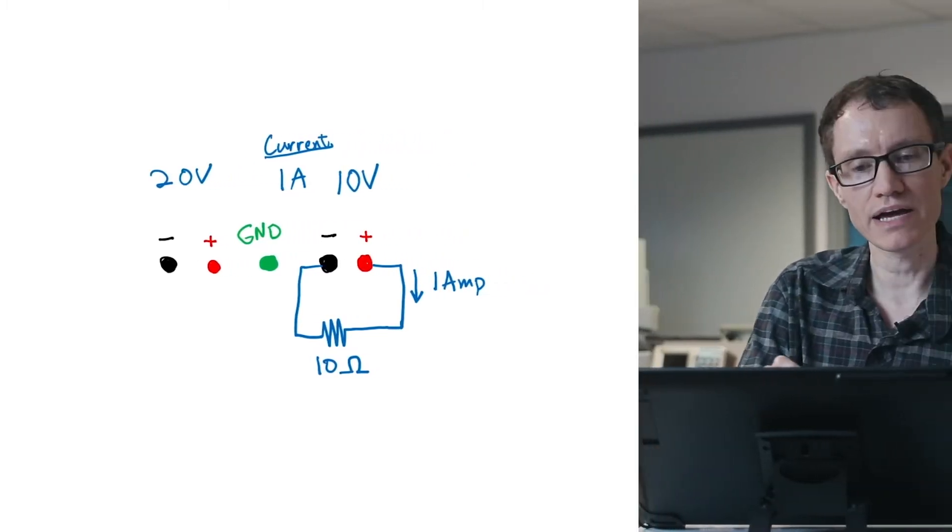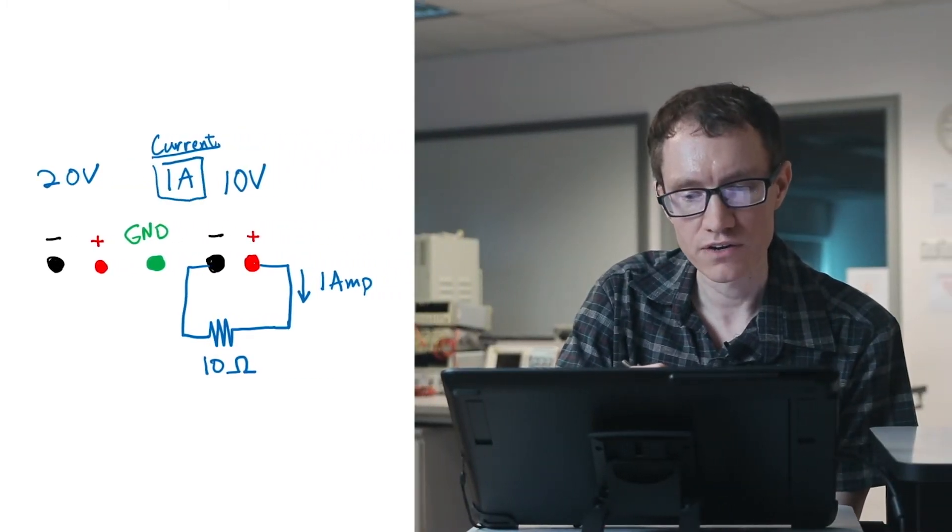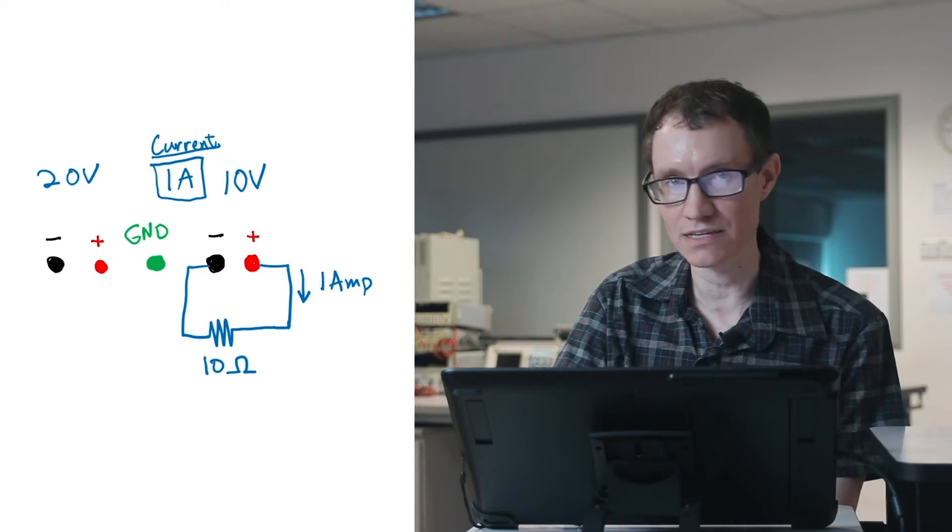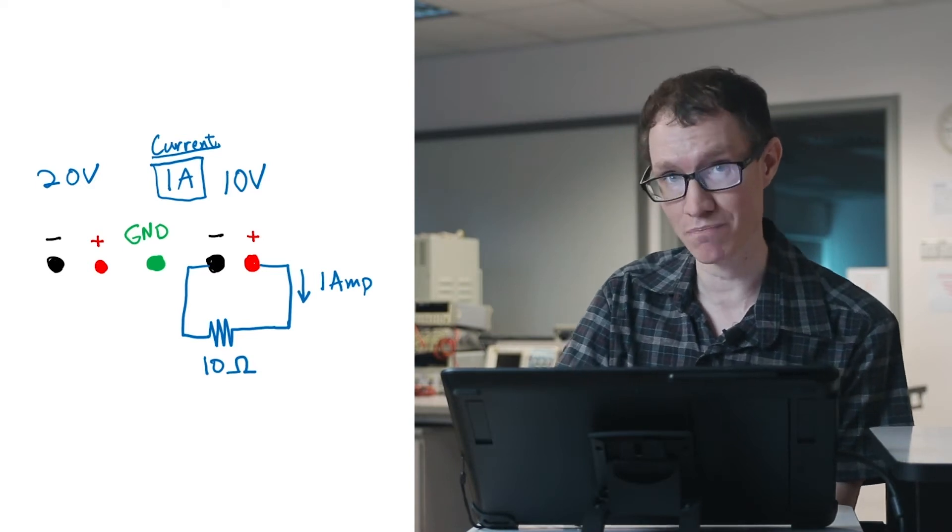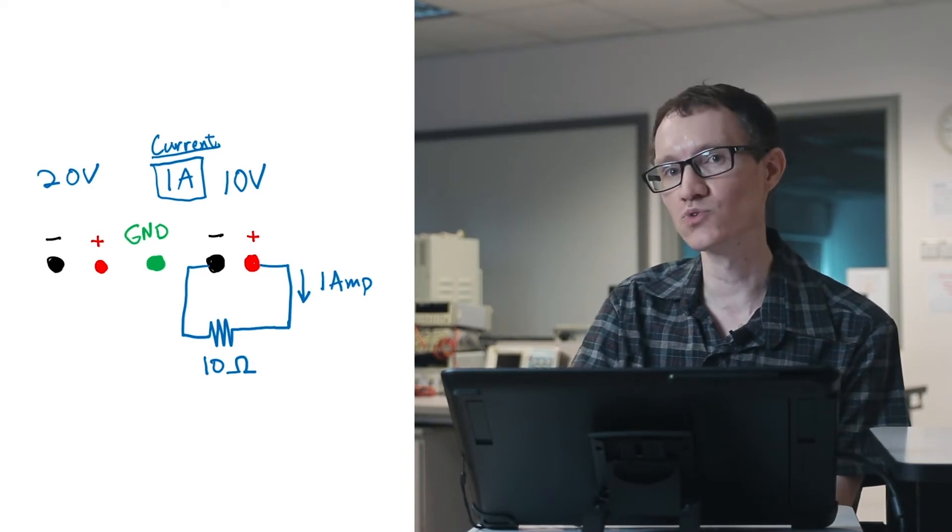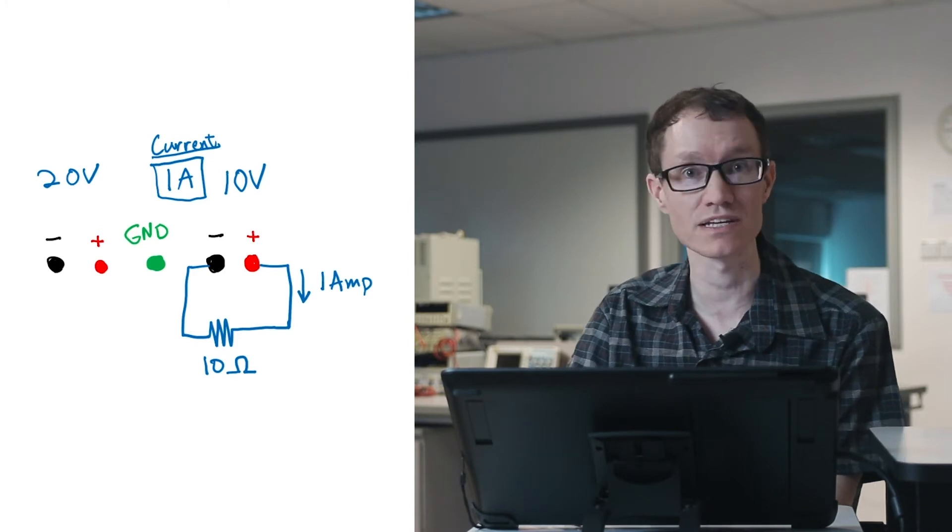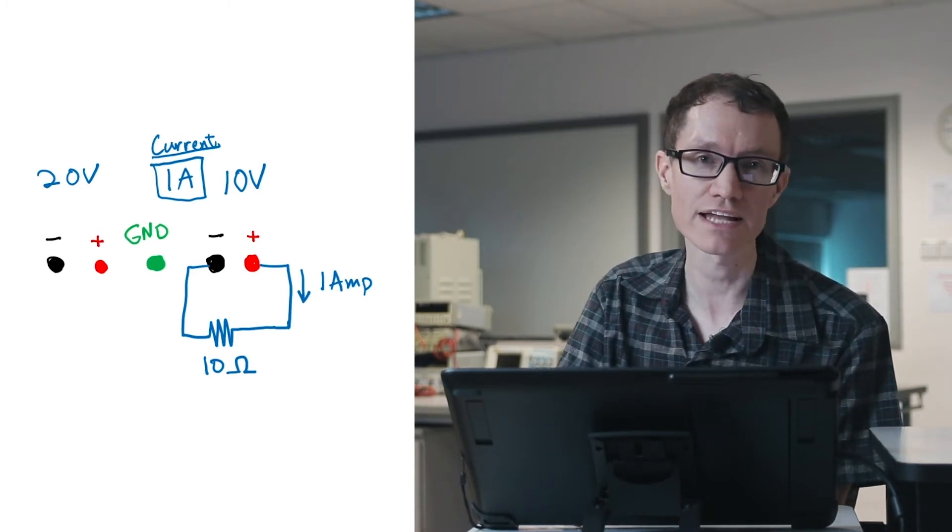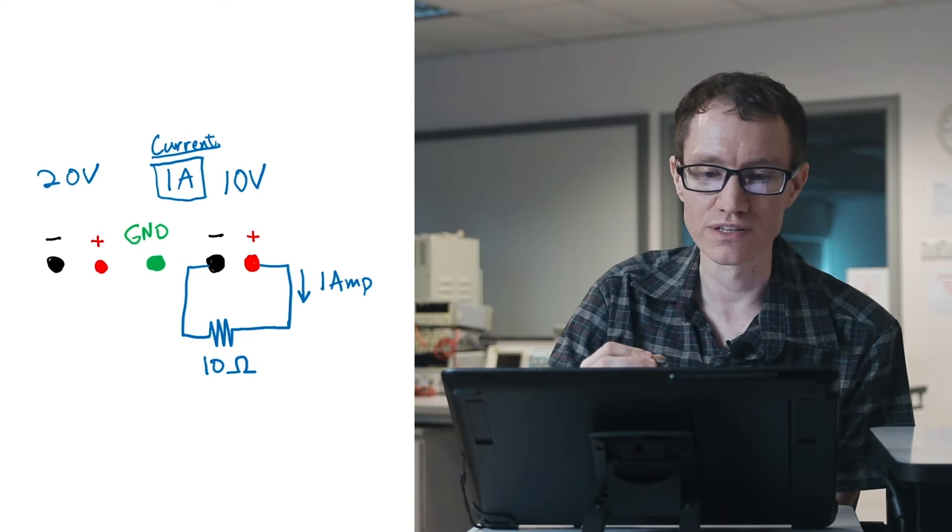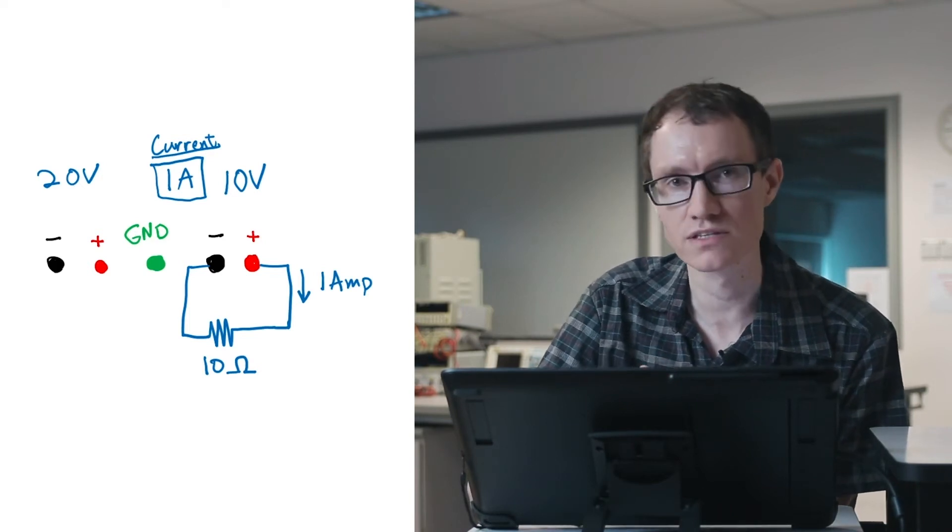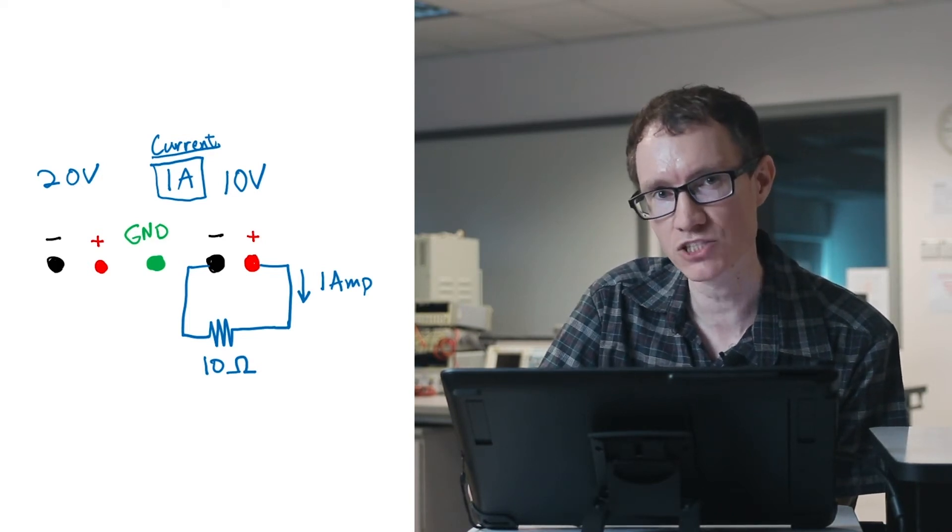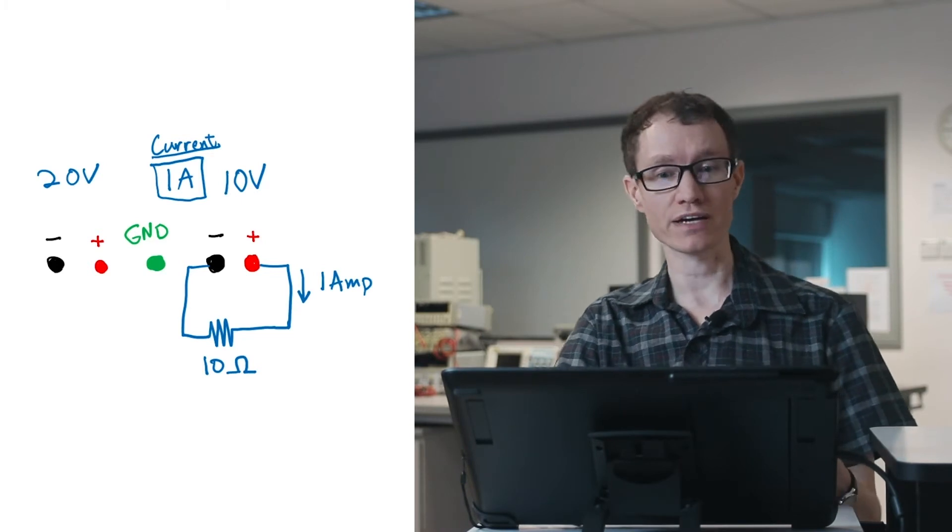But when the power supply is turned off, this number does not typically show 0 amperes. Because the display has a dual meaning with these power supplies and a lot of power supplies. And it's related to the limit. In other words, this power supply has a feature that can help you protect devices.